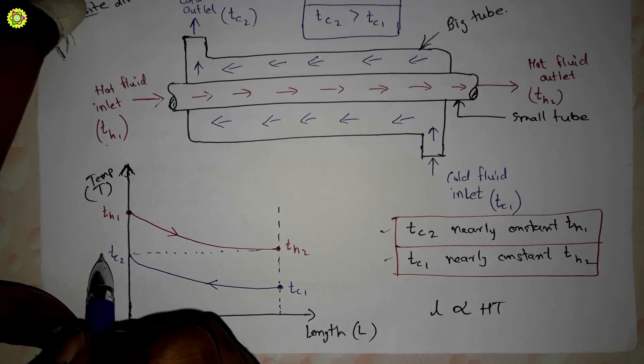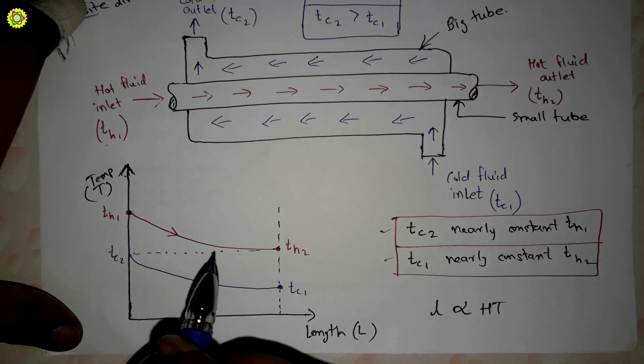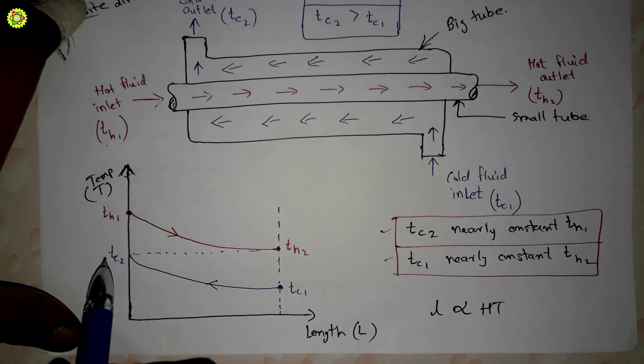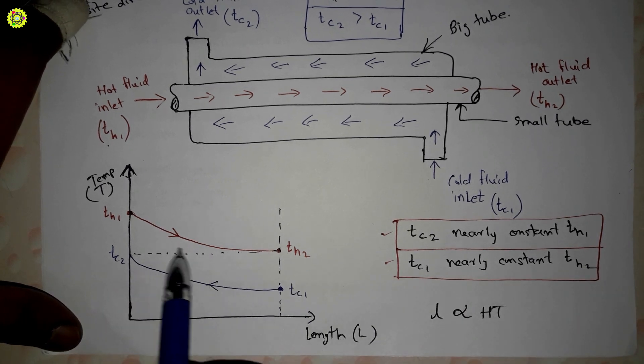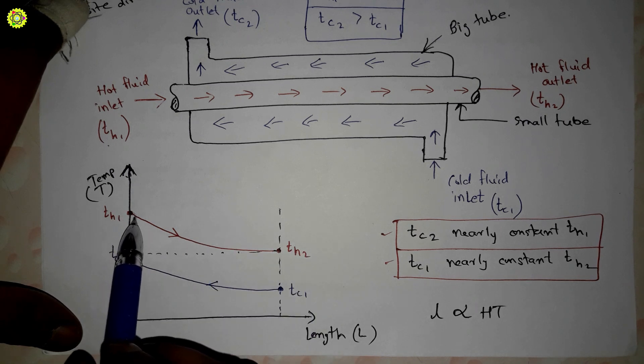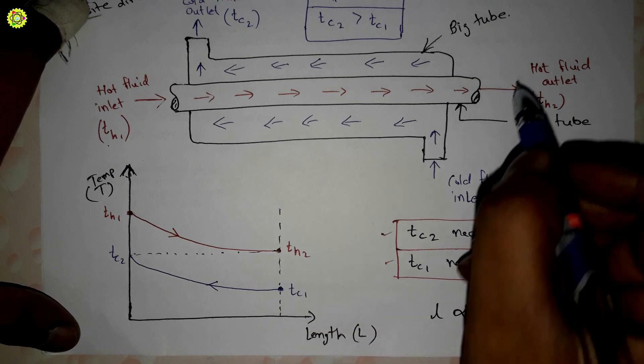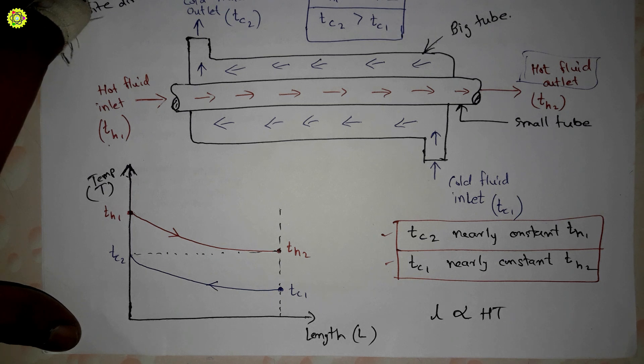So the graph shows the hot fluid temperature decreasing and the cold fluid temperature increasing. We get the cold fluid outlet near the hot fluid inlet side. Due to this counter flow arrangement, we get the maximum rate of heat transfer for a given surface area, which is why these heat exchangers are most favored for heating and cooling of fluids.